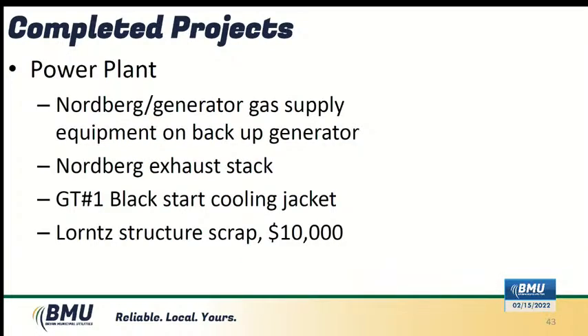Other completed projects: Nordberg generator gas supply equipment. We had issues getting the Nordberg out of the switchgear and back in — the switchgear didn't go back in, so we had to take it apart, lubricate it, and do a bunch of work. Overnight we found that with the power off on that section of the plant, it also turned off the gas and Nordberg controls. So we changed it to run on our backup power, so it would never be without power that way.